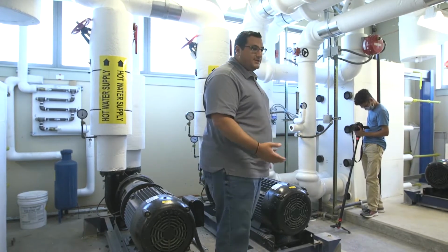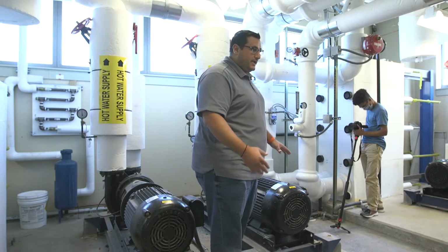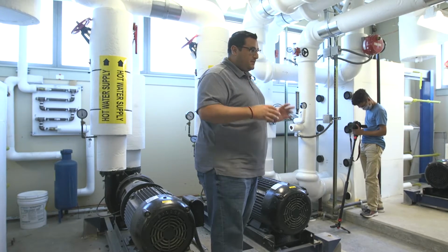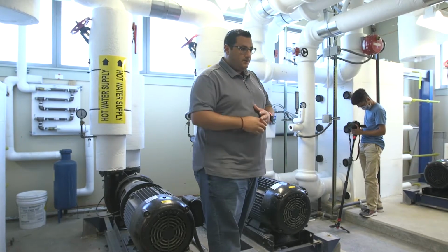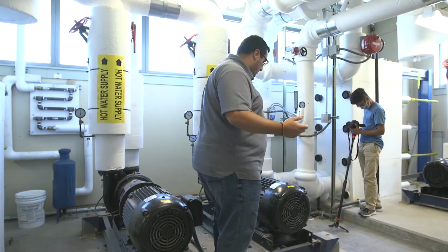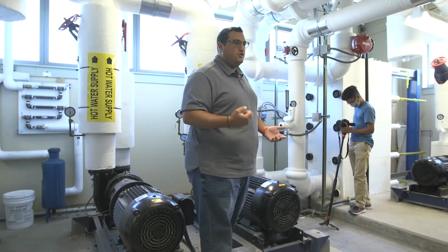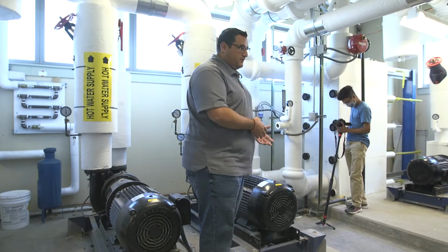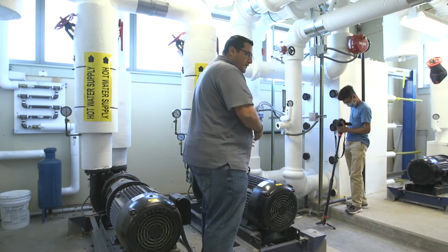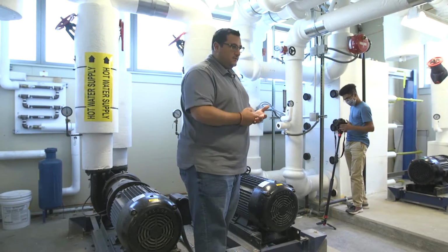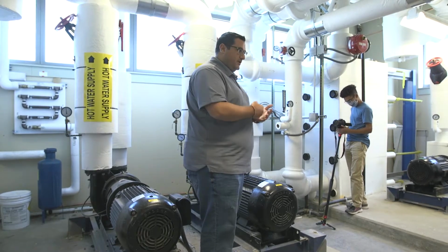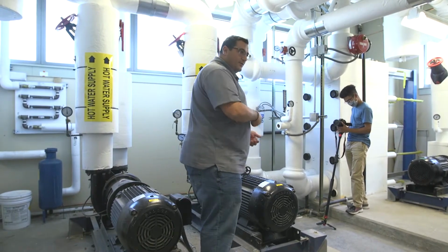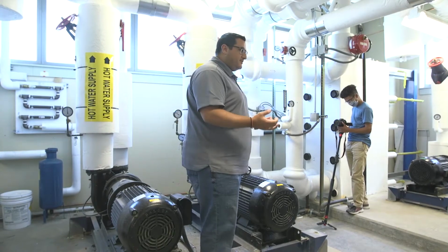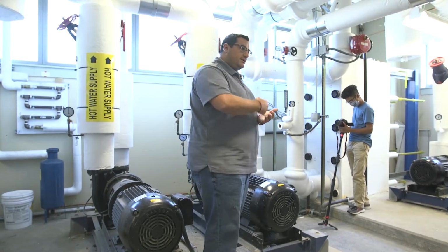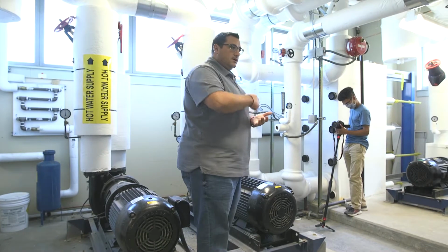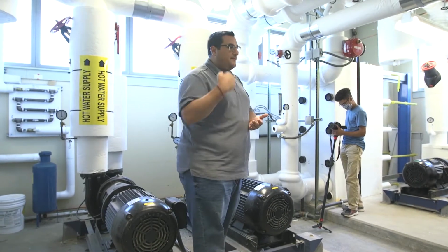As far as maintenance is concerned, it's a fairly simple thing. You grease the bearings as per the instruction and operation manual. The schedule, I think, is once a year, and it's one or two pumps. You have to be very careful when you grease pumps that you don't over grease. Bearings don't like to work in too much grease. They like to work in less grease, believe it or not. Everybody thinks we come here and we're just going to pump it, and the problems are going to go away. When you put too much grease, the bearings work too hard to push through, and you're actually causing more damage than you're doing any good.